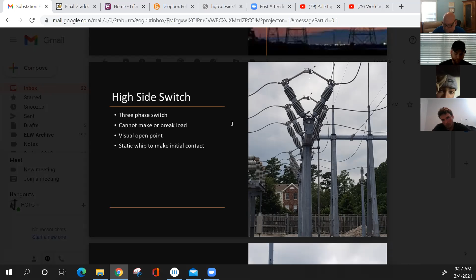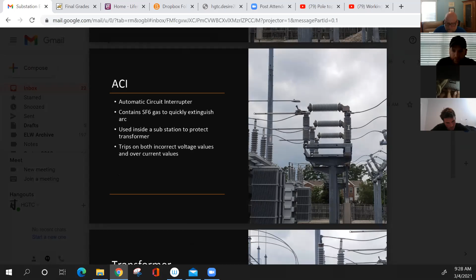Automatic circuit interrupter. The automatic circuit interrupter contains SF6 gas to quickly extinguish the arc. It is used inside a substation to protect the transformer and trips on both incorrect voltage values and overcurrent values. Guys, somebody tell me where this switch opens up. Anybody? Inside the top bushing? I'm sorry, I moved it. Inside which bushing? This bushing? No, the one in the middle. Yes, that's correct, Trevon. It actually opens up inside that tube with the SF6 gas in there to extinguish any arc that may take place in that tube.